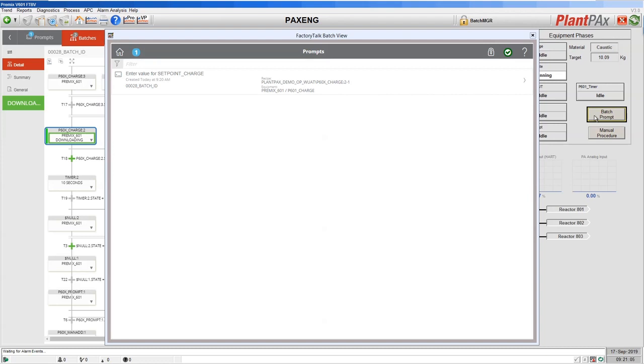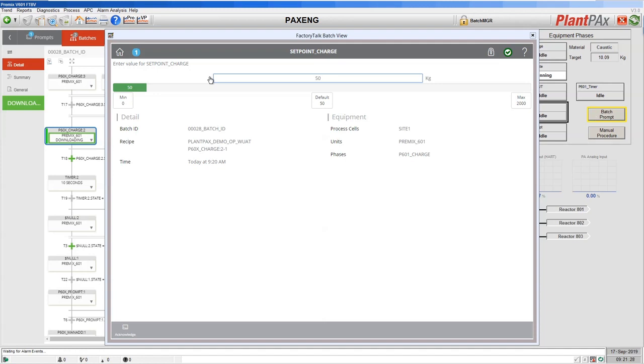This brings up the integrated FactoryTalk Batch control in the FactoryTalk View Site Edition environment, but this time set to just show prompts rather than the entire FactoryTalk Batch interface. We can see one prompt where we're being asked to enter a value for the setpoint charge and which recipe is asking for it. If we click on it we can see the details: the particular batch, the batch ID, the recipe that's running, the unit, the default value, and we're asked to either change that value or acknowledge and accept the default. If we look at the web interface, it is exactly the same.